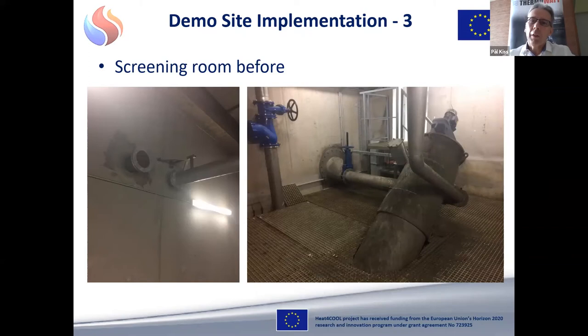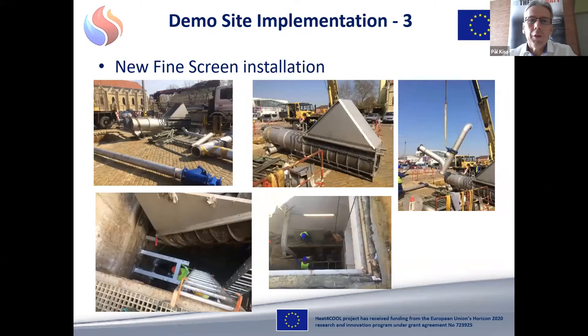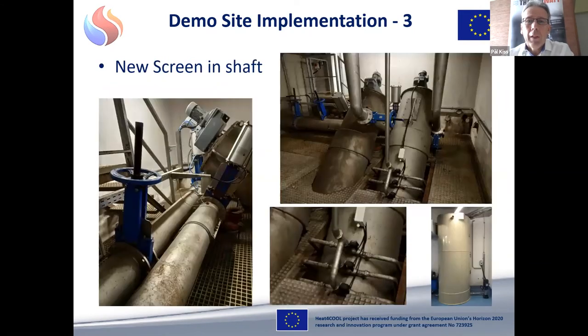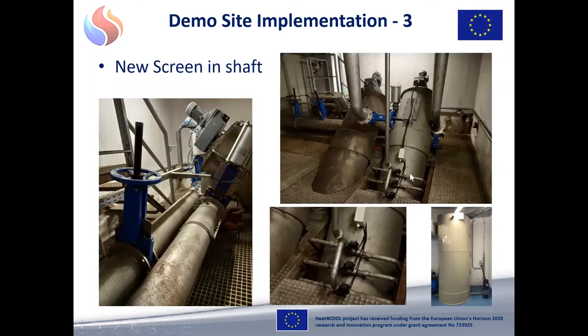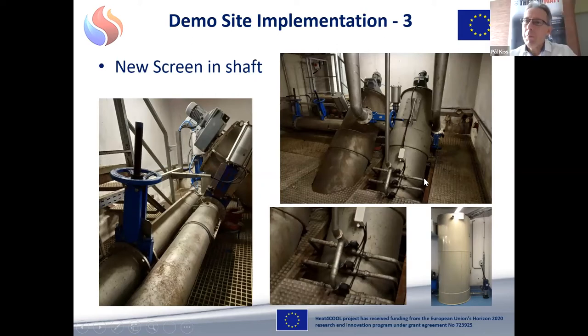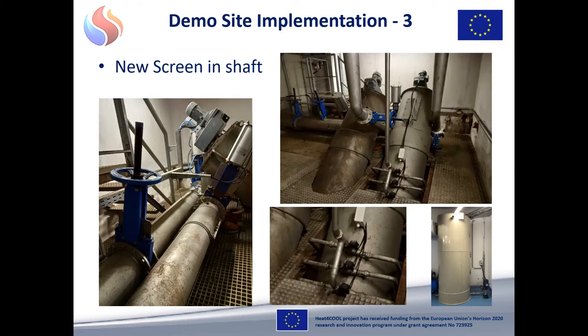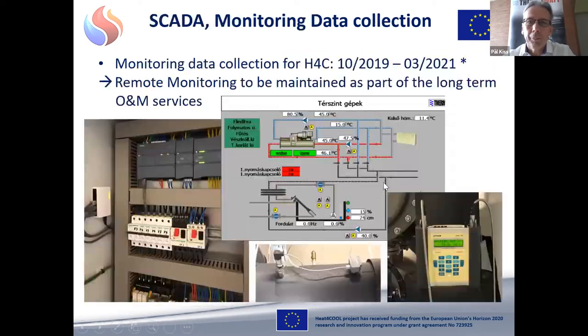And the COP that we achieved is between 3 and 4 at this stage, because we still operate at high temperature. But coming back to the screen installation, here you see the screen installation being put in place. And then the new screens on site, where you can see the washing system that we invented to do the easy maintenance of the system. So the aim here is to operate a large-scale system without being on site and doing a very efficient heat exchange for the whole system.